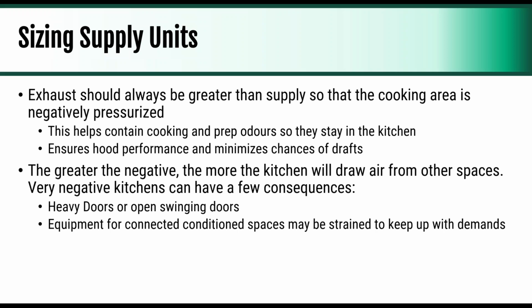Obviously, just having a negative kitchen isn't going to eliminate drafts. You need to distribute the supply air evenly in order to do that, but it does minimize it. And then lastly, the greater the negative, the more the kitchen will draw from other spaces. So very negative kitchens will have some consequences, but we do see people going pretty negative on kitchens if they want to bring in, say, conditioned air from other spaces, because they're not conditioning the kitchen air. But heavy doors or open swinging doors are two of the things you'll see with a very negative kitchen. And then equipment that's in connected conditioned spaces may have a hard time keeping up with demand.